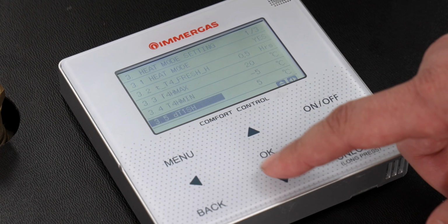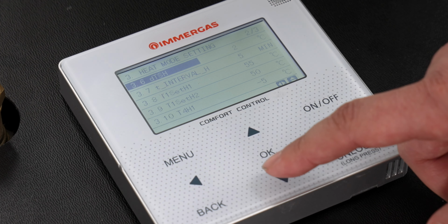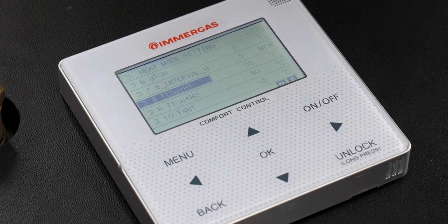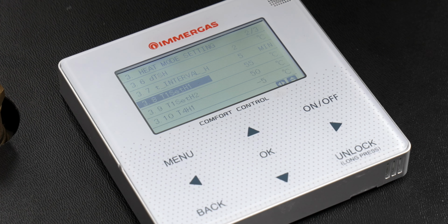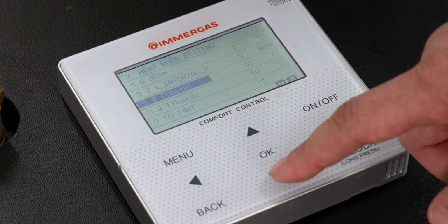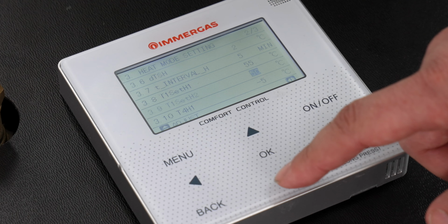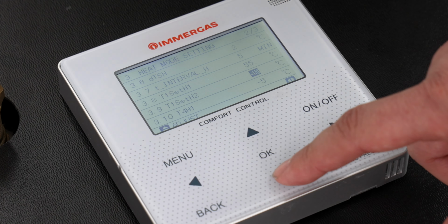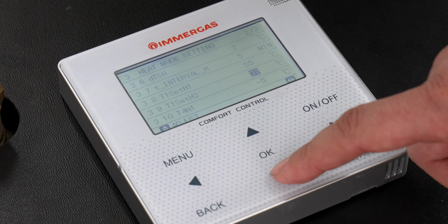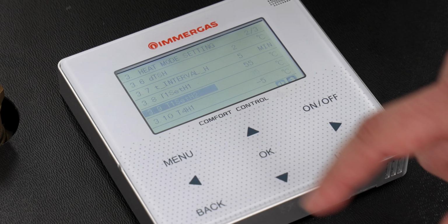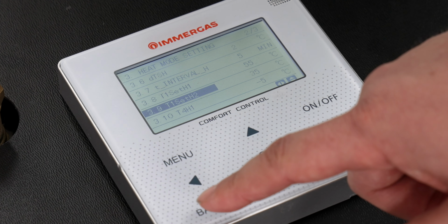If you scroll down again to the next page, it's got your flow and your return temperature. At the moment it says 55 50. This is only set up so high because we're in the training school. We would maybe keep it anything between 45 and 55 on your flow, and then on the bottom one you maybe want to take that down to about 35. So we'll go 55, 35. Press OK. That's now set up.